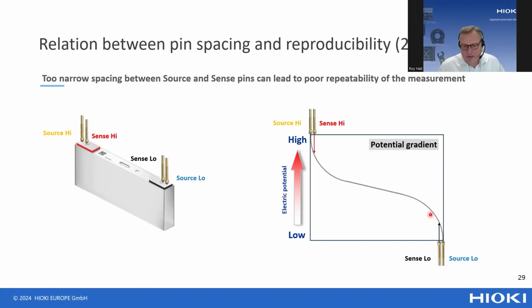It's very often considered that the best results for an internal resistance measurement are achieved when the probes for the source and the sense are very close to each other. However, if you look at this, you can see that when you put them very closely together, you're going to measure at the very steep part of your potential gradient slope. If you want repeatable measurements and good reproducibility, that is very difficult on this very steep part of the slope. The slightest changes in positioning will have an impact on the voltage that you measure, and therefore on the repeatability and the reproducibility of your measurement.